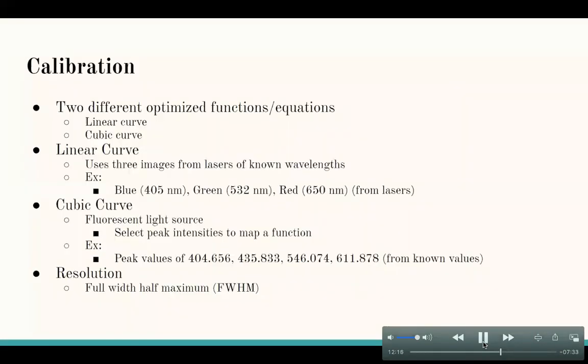To use a spectrometer for mapping a spectrum from an image, it needs to be calibrated to provide an optimized function. For this system, there are 2 ways to calibrate the spectrometer, with a linear or a cubic curve. The linear calibration uses 3 images from lasers of known wavelengths. For example, there could be a blue laser, a green laser, and a red laser with wavelengths of 405 nanometers, 532 nanometers, and 650 nanometers respectively.